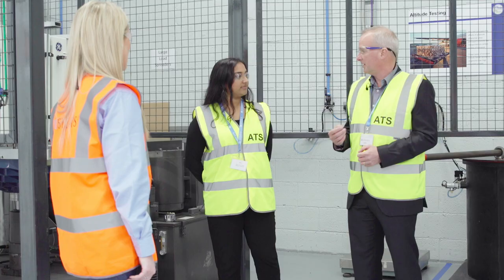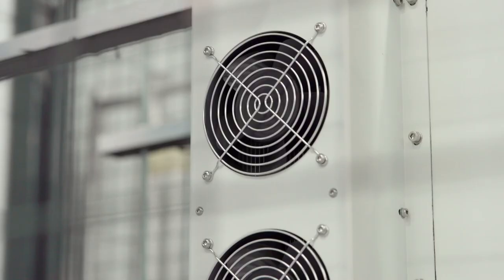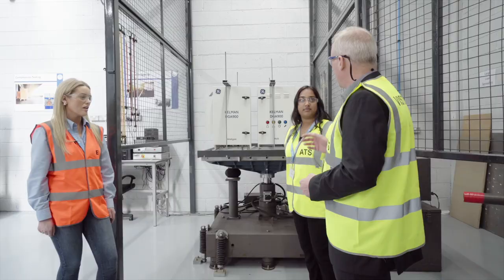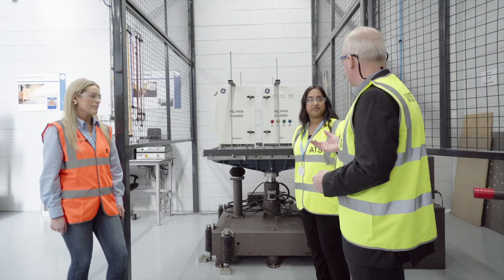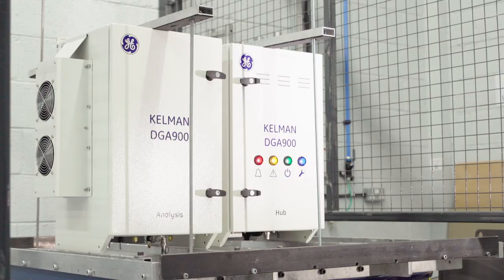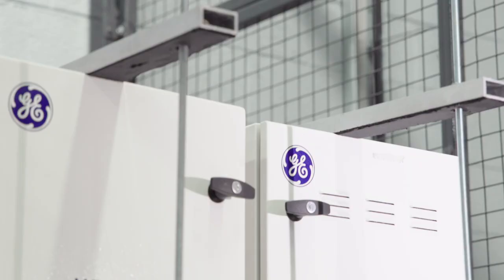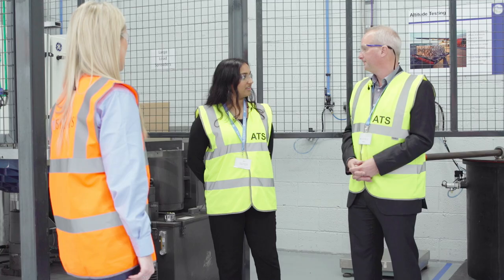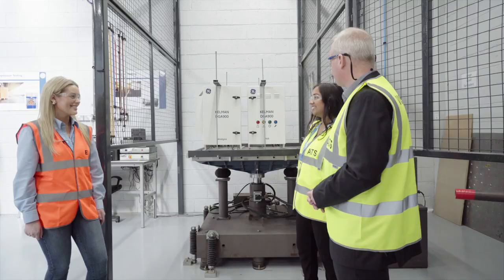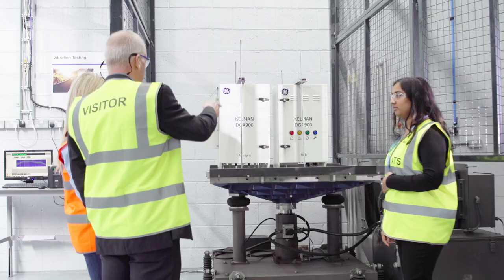After vibration testing that we would do here, we would then take it back to the GE facility and make sure it's functionally performing as expected through further testing. What we can also do here is simulate the type of vibration that the unit would be exposed to when it's being transported to the site or to the customer, and still make sure that it performs as expected. That's great, I understand. Shall we see how it works? Yes, absolutely.